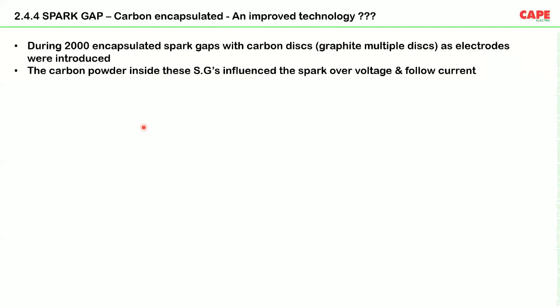During 2000, sealed spark gaps came into the market, called encapsulated spark gaps. That means the blowout is not coming out of the device, due to various technologies. The arc which is created is encapsulated inside the device. One of the initial technologies which came is called graphite multi-disc technology. That means there are several graphite electrodes connected in series or parallel inside.